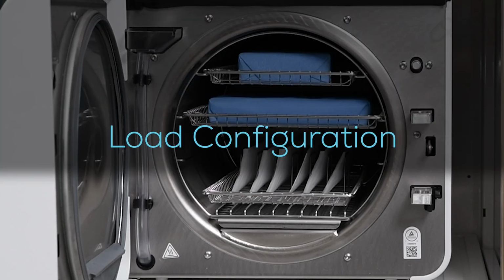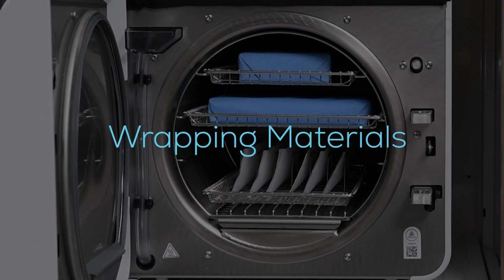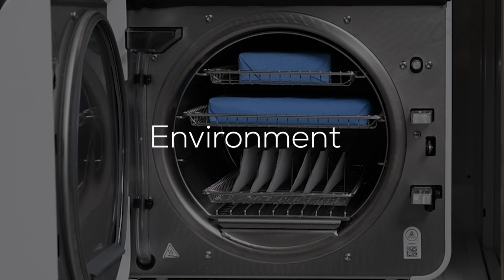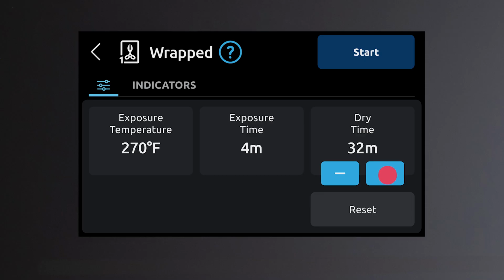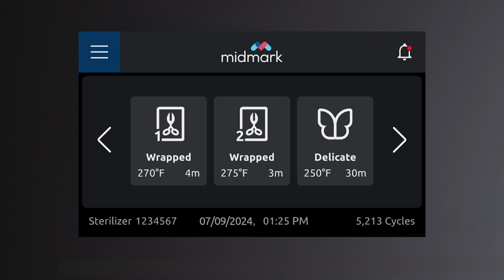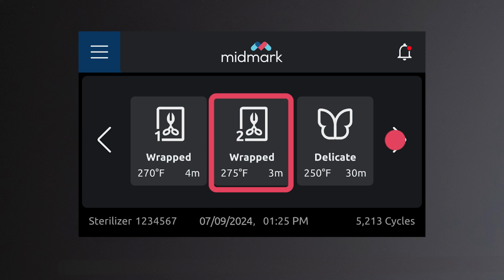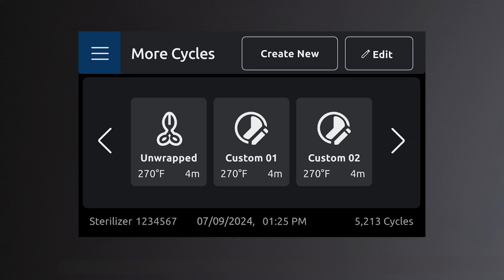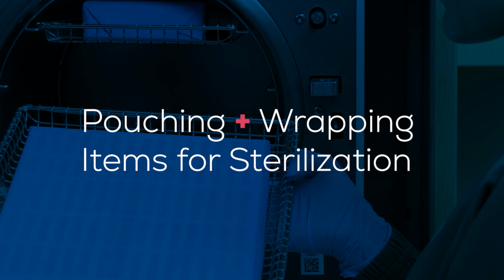Variations in load configuration, size, wrapping materials, and the environment may require the operator to increase the default drying time to ensure all packing and instruments are completely dry. When sterilizing a load with one or more handpieces, utilize the wrapped 1, wrapped 2, or custom cycle, depending on the handpiece manufacturer's instructions. Pouching and wrapping items for sterilization.